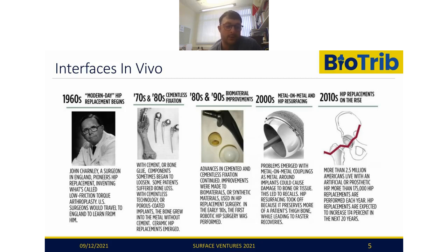And so we ultimately arrived at ultra low wear bearing combinations. But in doing that, it introduced different problems. Modularity introduced things like crevices, where fretting corrosion can take place, and whilst you give with one hand, you take with the other. Ultimately there were then complications in terms of fretting corrosion, which have emerged and have really stayed around up until today.